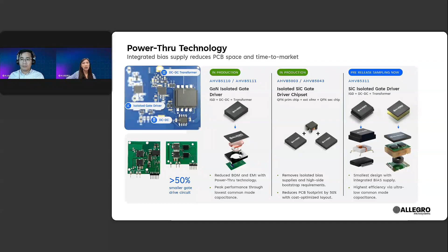Now I'd like to use solid-state breaker as another example. As we talked about at the very beginning, in the new AI power architecture, the 800-volt DC link between the power rack and IT rack needs fast and reliable protection. But SSCB design is not easy. First, the system needs to support 800-volt VDC, so the isolation requirement becomes higher. Second, thermal management is critical.